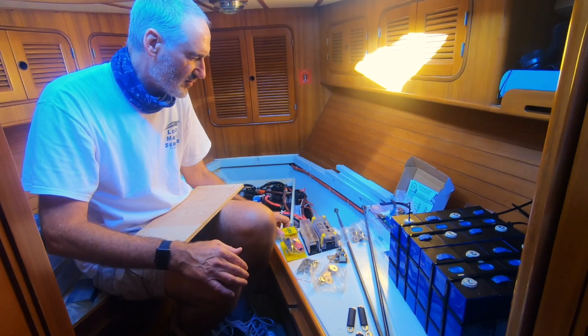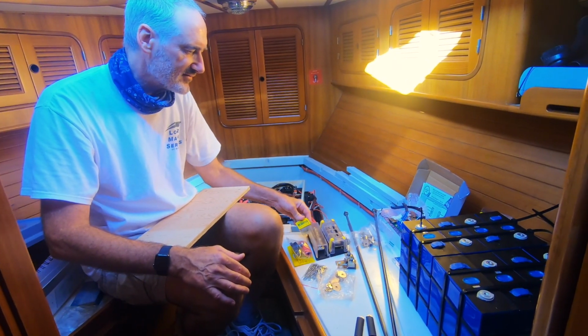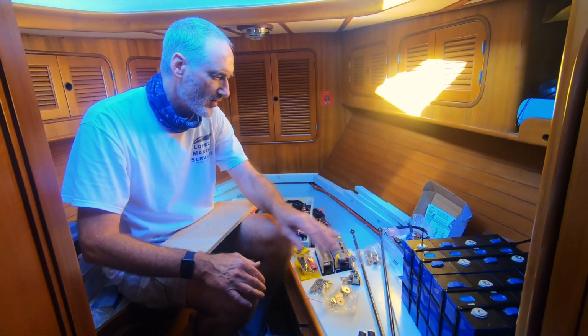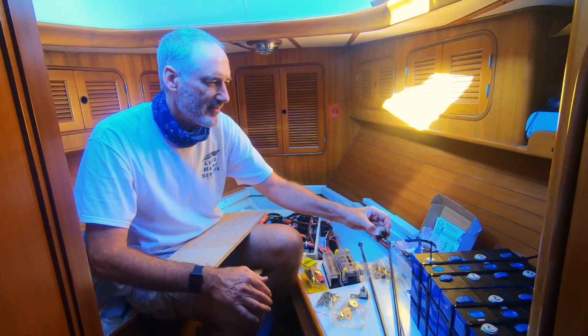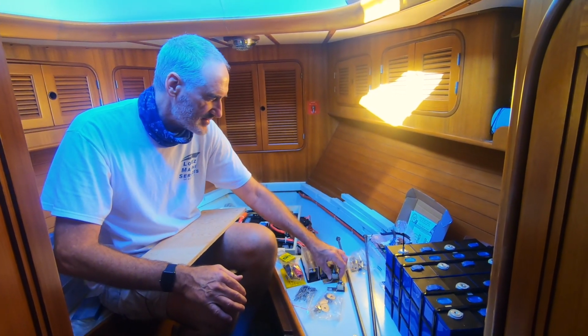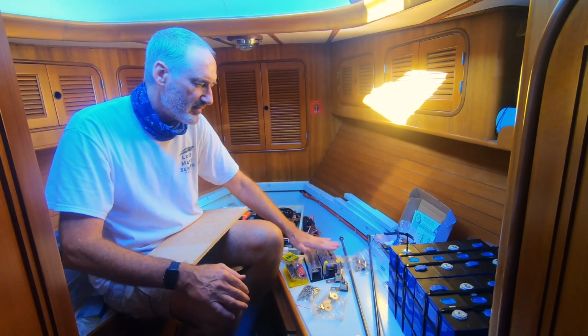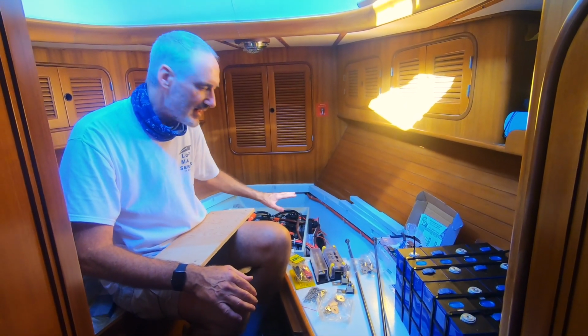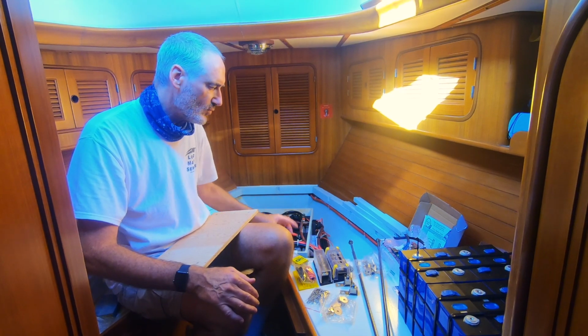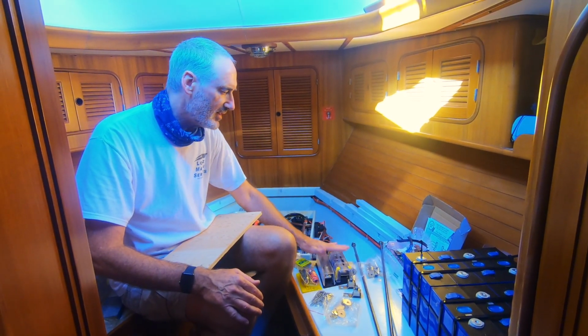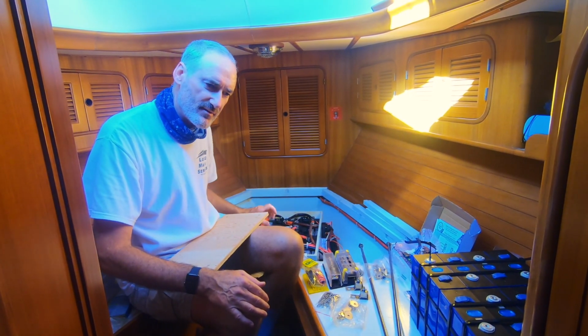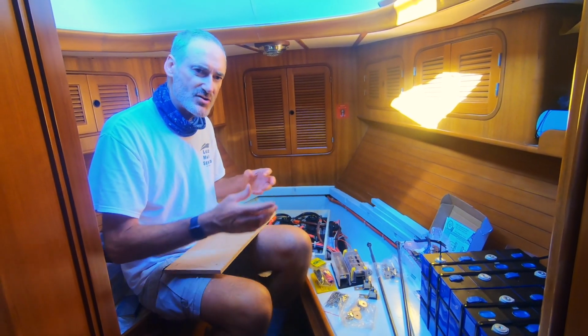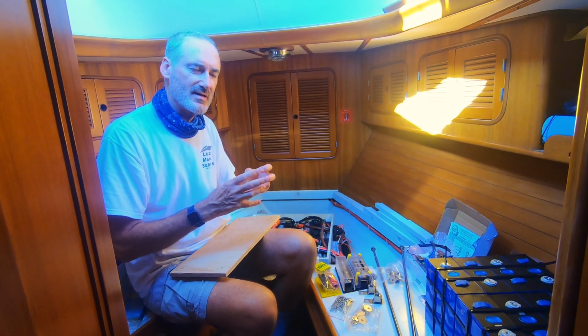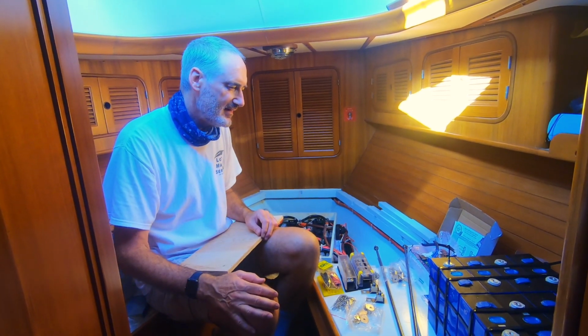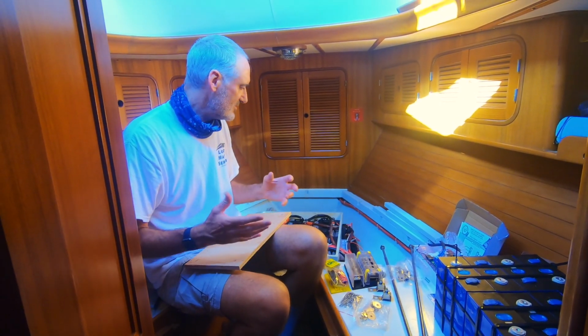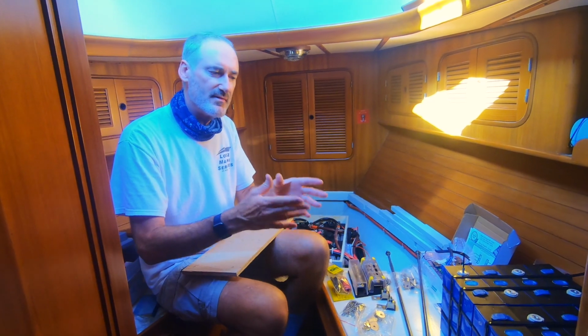I have a 400 amp T-class fuse for the total bank. Each battery will have a 300 amp terminal fuse on it, and we'll have new bus bars so we can clean up all this wiring and make sure everything is wired to a bus bar. We'll have everything going through the same shunt, which measures the amount of capacity used from the battery bank, and this will allow us to better manage and monitor the batteries.